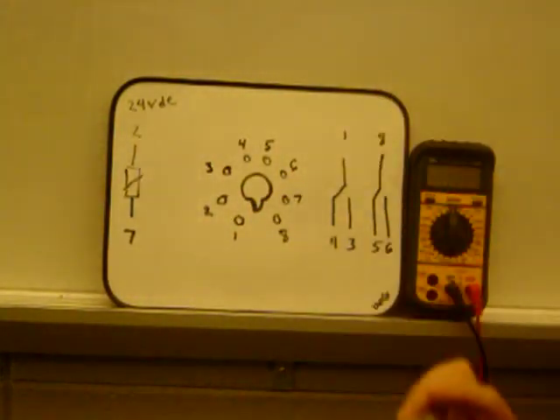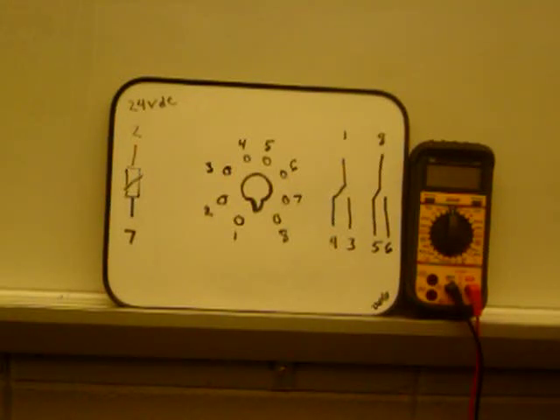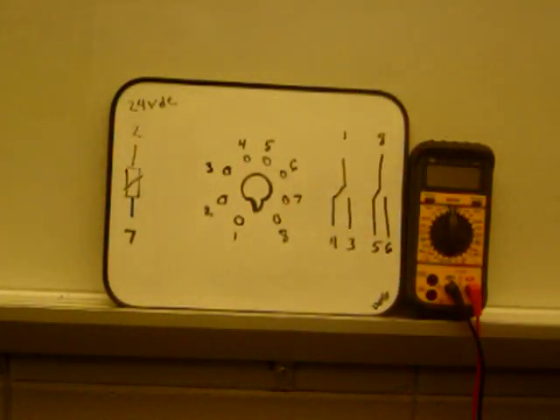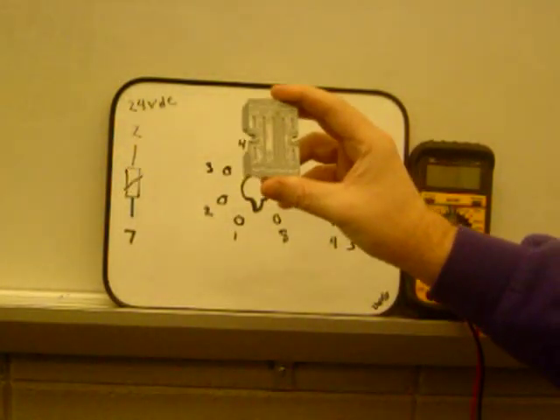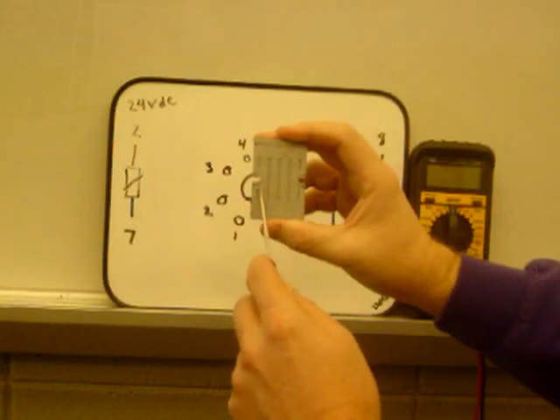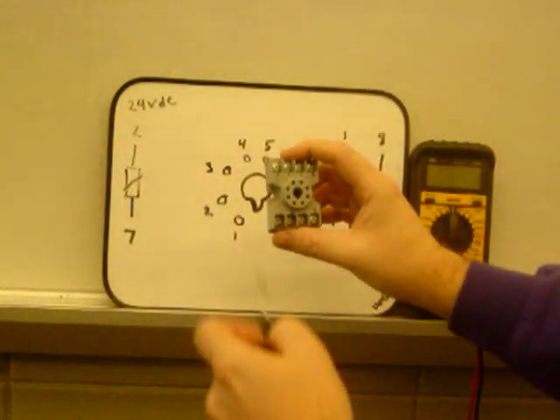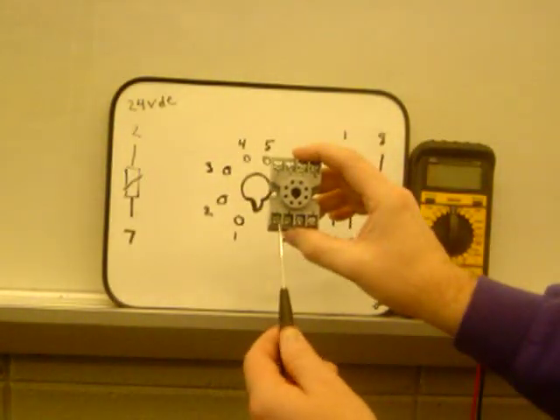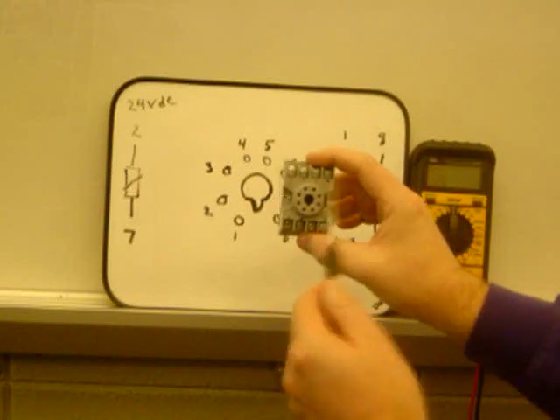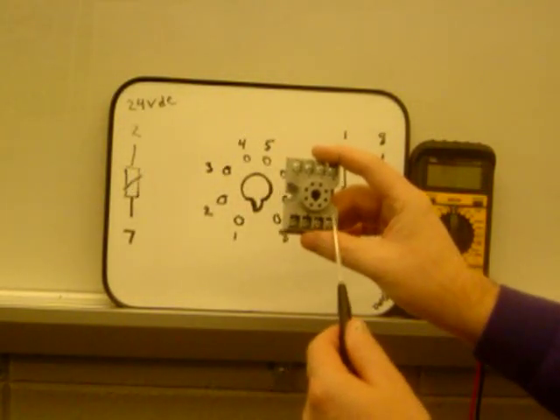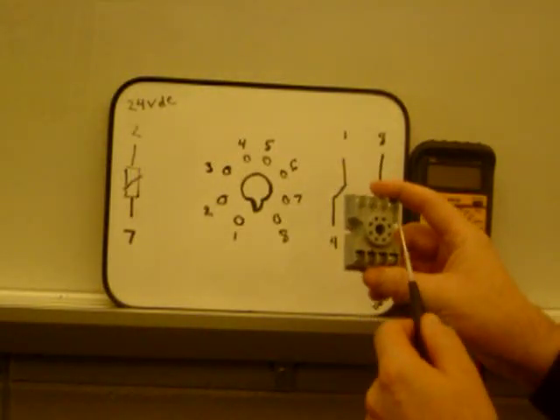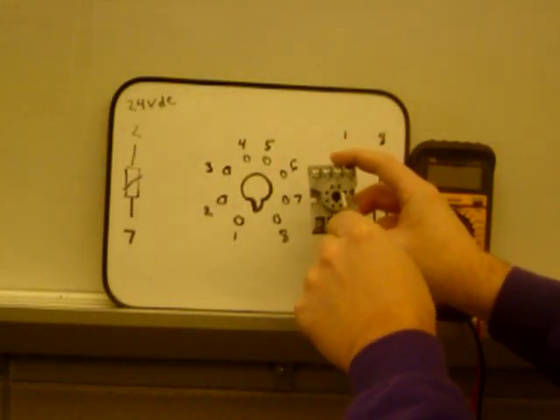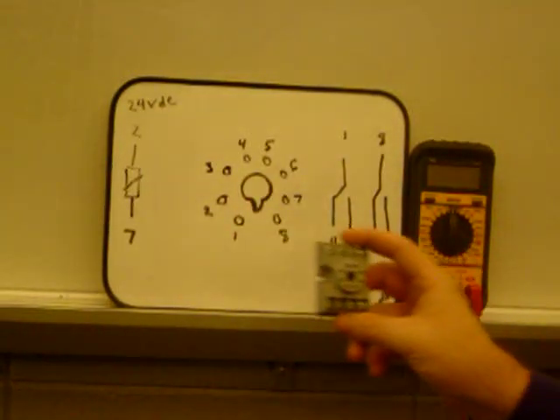This is one type of relay base. If you're building a project, you've got to be careful what kind of relay base you get. It's very handy to snap something like this on a DIN rail. You can take it off. You get a relay base like this, you have no DIN rail options. This relay is set to simply go into an area and just be held in place with the screws. See, you've got your standard eight pins. I was actually able to highlight this one with a black marker, three, four, five, six, seven, and eight going around. So again, the screws match up with terminal numbers and the terminal numbers match up with the relays. Very important.